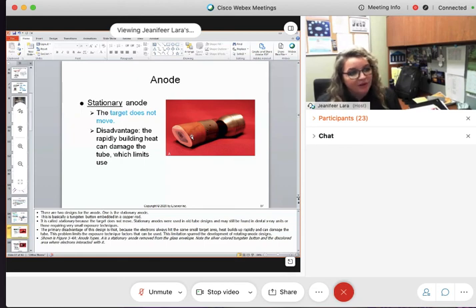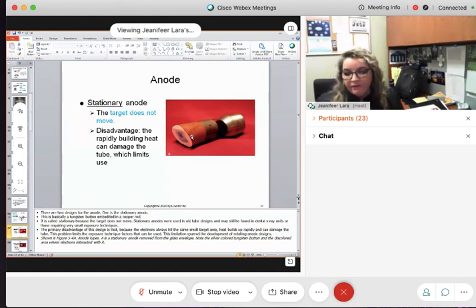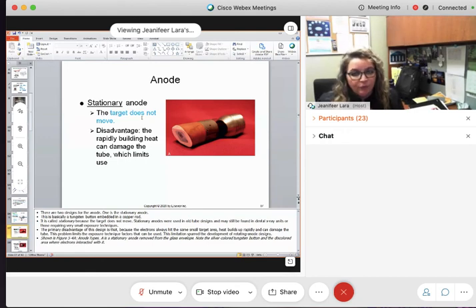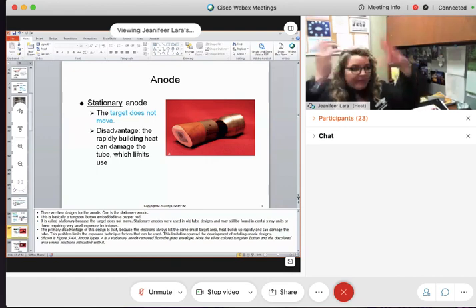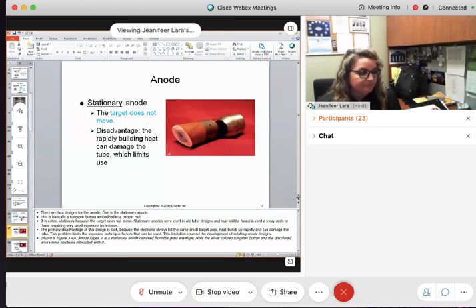99% of electron flow is converted into heat, and only 1% is converted into x-ray. Not efficient at all — but we have no better way. When you have a stationary anode, the target does not move, the disadvantage is you're building up a lot of heat. If there's too much heat, your machine shuts down if it gets overloaded.